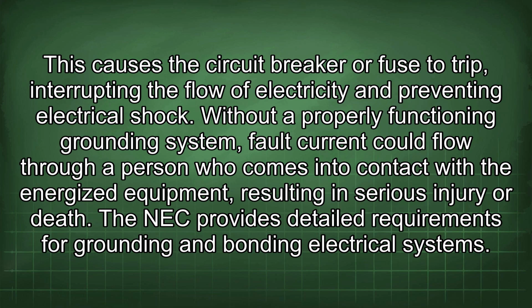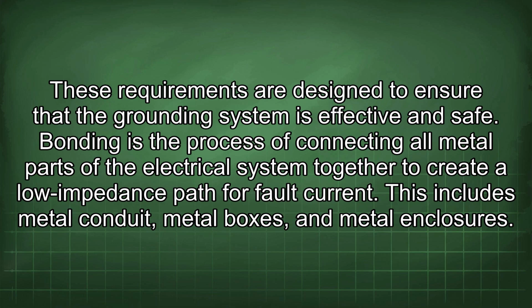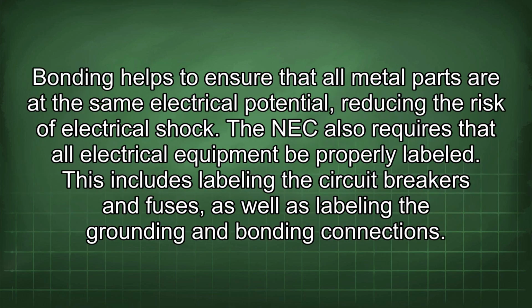The NEC provides detailed requirements for grounding and bonding electrical systems. These requirements are designed to ensure that the grounding system is effective and safe. Bonding is the process of connecting all metal parts of the electrical system together to create a low impedance path for fault current. This includes metal conduit, metal boxes, and metal enclosures. Bonding helps to ensure that all metal parts are at the same electrical potential, reducing the risk of electrical shock.